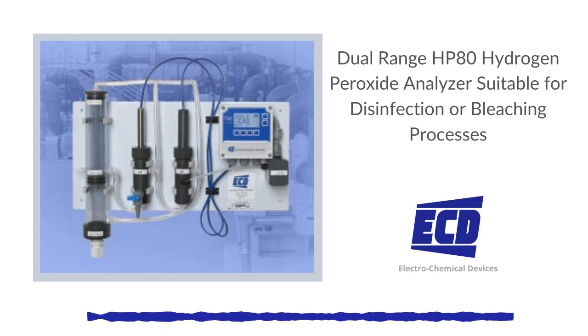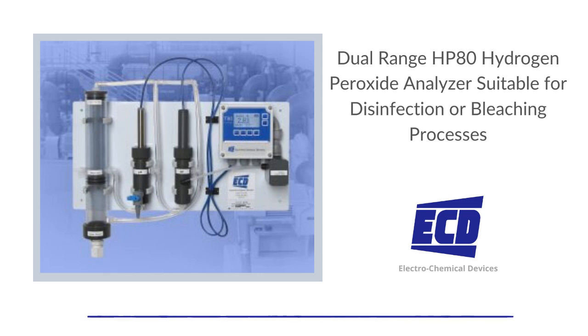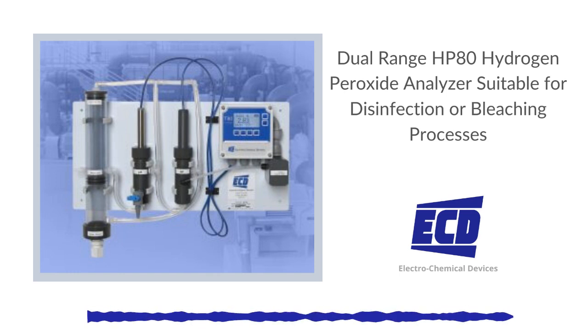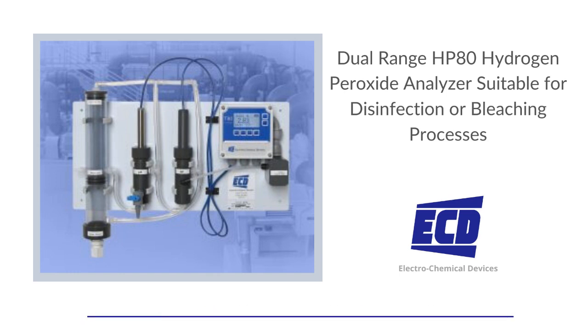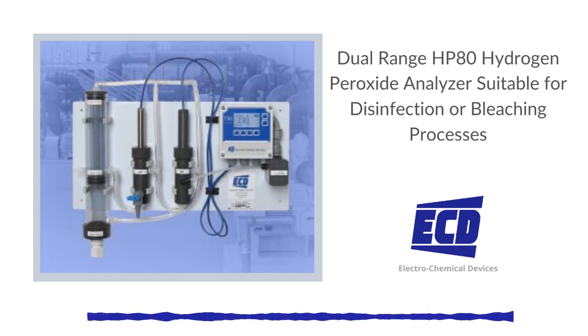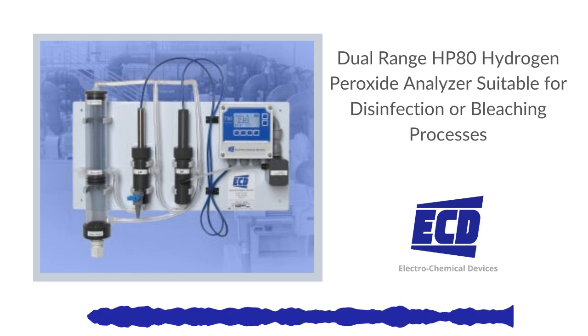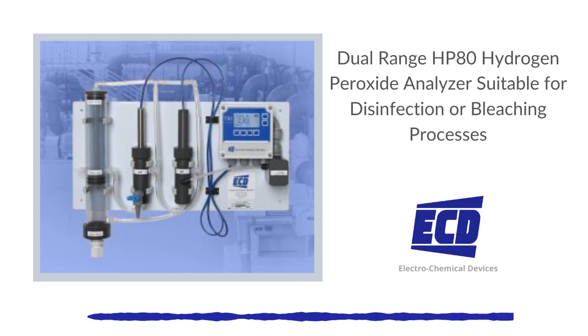An optional sensor auto-clean configuration is available, which includes a solenoid-actuated spray cleaner that provides either a 30 pounds per square inch process water or air. The spray cleaner removes films from the sensor head, which over time can affect measurement accuracy. There is rarely a need for manual wiping of the sensor head by maintenance technicians with a spray clean configuration. The sensor's maintenance requirement is typically to replace the electrolyte every 6 months and replace the membrane cap once a year.